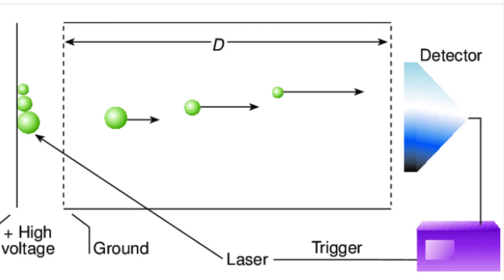After the ions leave the quadrupole, they are analyzed using the time of flight mass analyzer. Here, all of the ions are accelerated with the same force and the resulting differences in travel velocity through the free drift region of the time of flight analyzer occur as a consequence of the size of the ions. Subsequently, by measuring the time it takes them to reach the detector at the end of the drift region, we can calculate their masses.